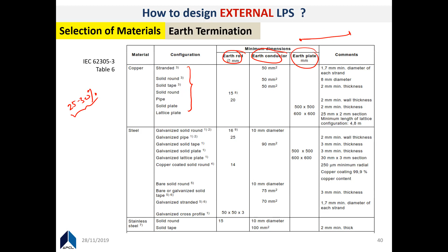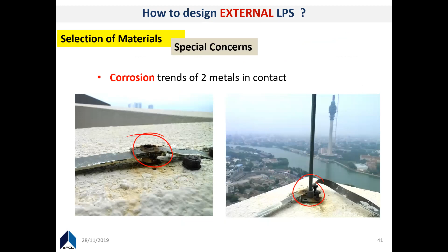And you can either have earth rods or a conductor, meaning even a tape or a rope underneath the ground, and you can even have an earth plate. All right, okay. So this is what I mentioned. When you are choosing the materials, you have to be careful about the corrosion properties. See, during an inspection, we found this being corroded. So there will be no use of the lightning protection system if these connections are gone. Okay, so you have to make sure of the corrosion.